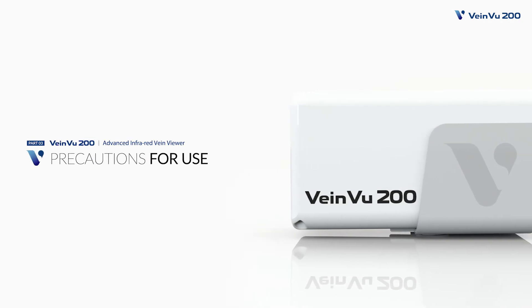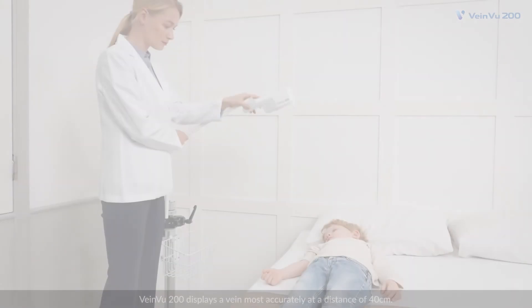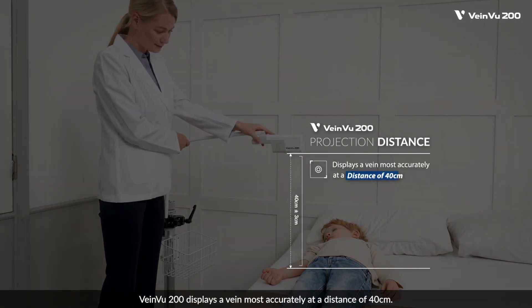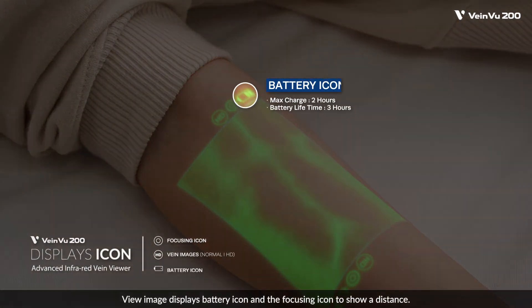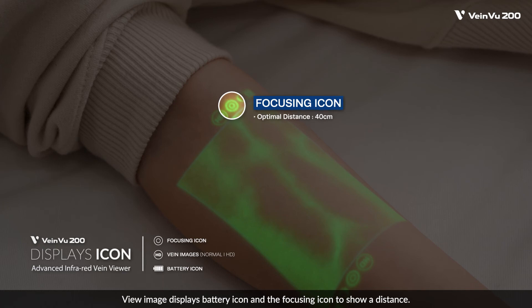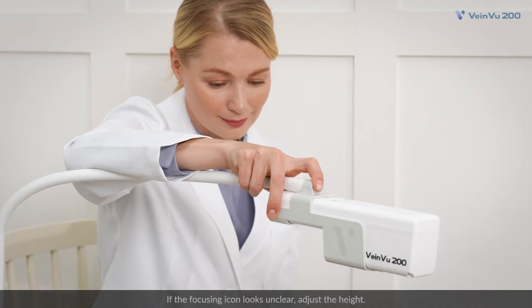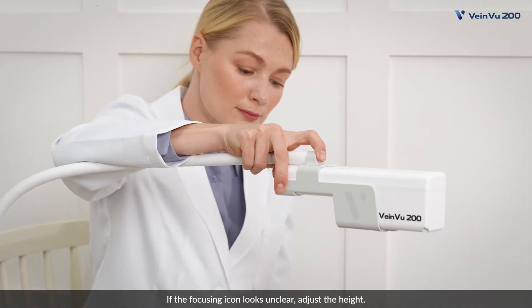Precautions for use. VeinVu 200 displays a vein most accurately at a distance of 40 centimeters. The view image displays a battery icon and a focusing icon to show distance. The focusing icon appears clearly at a distance of 40 centimeters. If the focusing icon looks unclear, adjust the height.